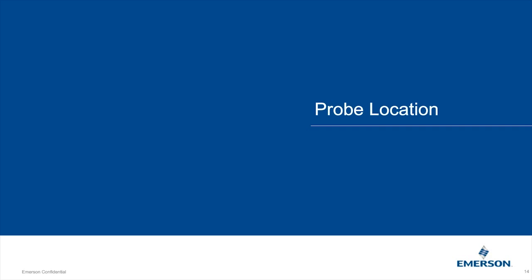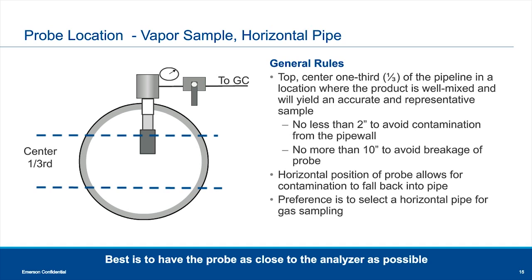For probe location with a vapor sample in a horizontal pipe, the ideal position is center one-third — the probe should be about one-third of the way down in the center section. Getting too close to the pipe wall picks up contamination. Probe length should be between 2 and 10 inches — no longer than 10 inches, as a long thin probe hanging in a pipeline can snap from a sudden gas flow, sending it downstream.